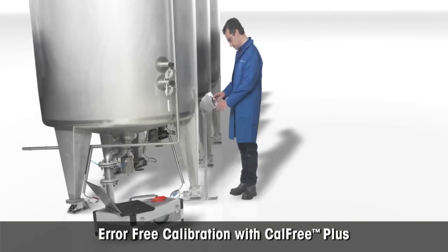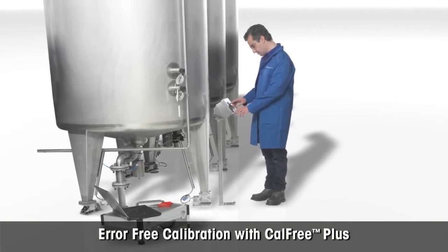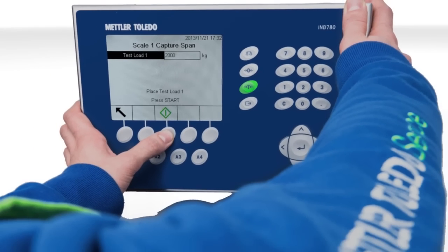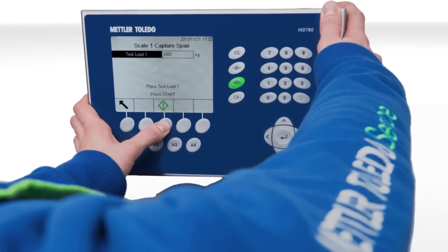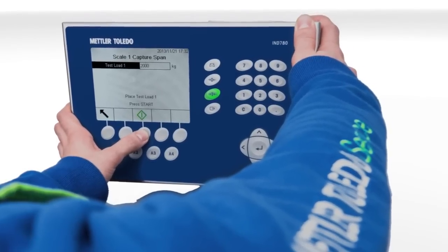When calibration with test weights is impractical, Power Mount systems allow easy calibration with CalFree Plus. Power Cells provide all relevant information to the terminal for a quick and easy calibration, even compensating for local gravity.